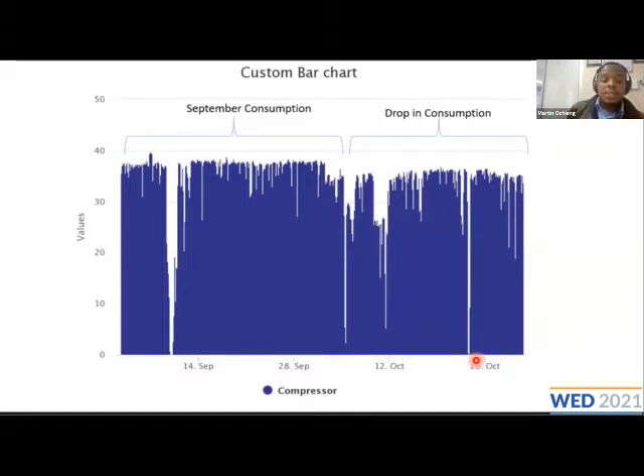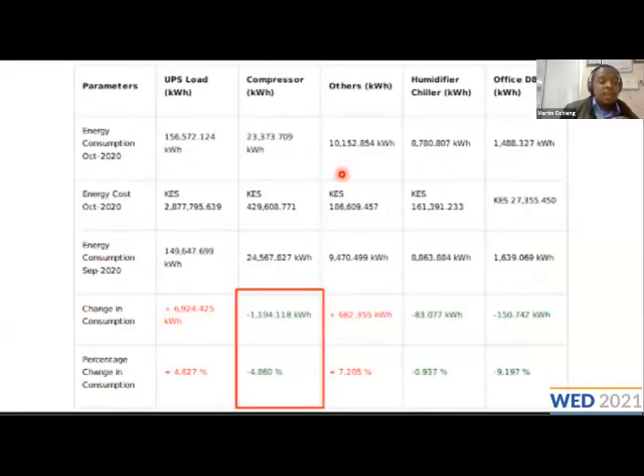And as you can see, there's a significant energy consumption reduction there, as can be demonstrated by the monthly report developed by the EGOS energy platform. For the compressor right down here, there's a reduction of around 4.8, close to 5%, in energy consumption for that particular utility, which amounted to around 20,000 Kenya shillings, roughly $200.